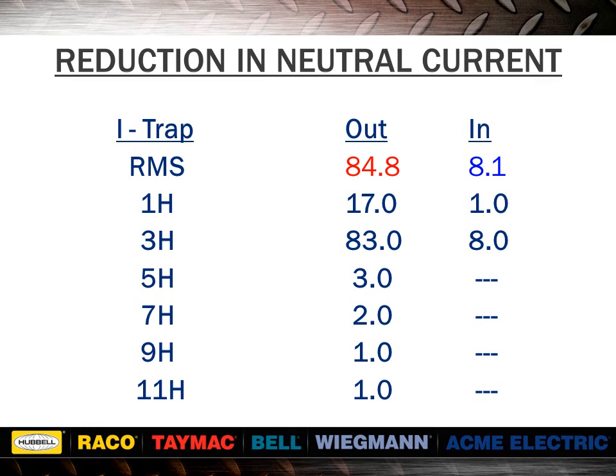Here we see that the total neutral current of 84.8 amps is greater than the highest phase current of 63.2 amps. Notice that the total neutral current has been reduced by almost 90%, from 84.8 to 8.1 amps.